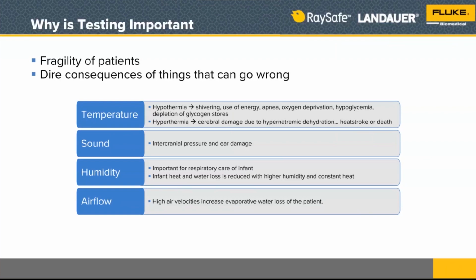The airflow, as I said before, if it's too high, it will cause the moisture that the baby needs in their skin and everything to evaporate. And that's not good for the patient. And if it's too low, we don't get the right amount of mixing of the oxygen and the temperature in the chamber. So those are some of the things that can go wrong if we're not careful.